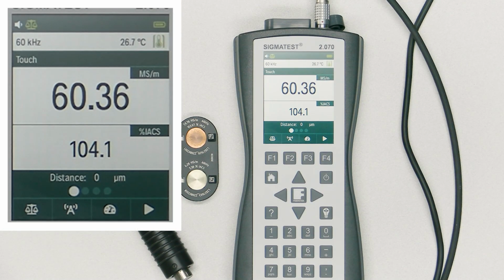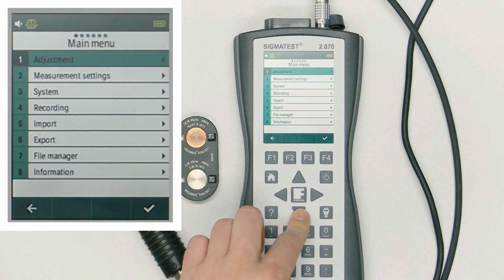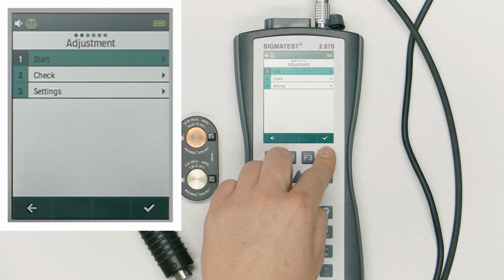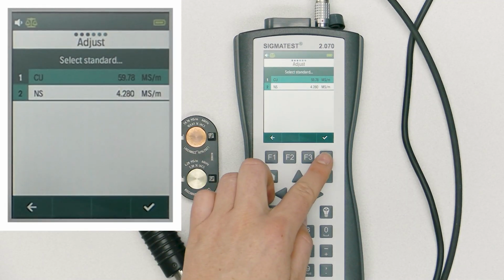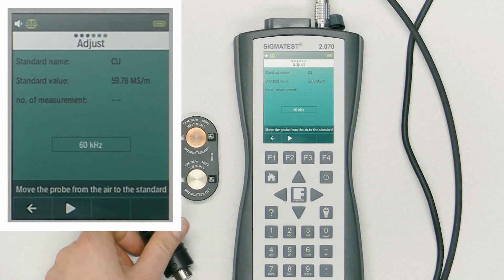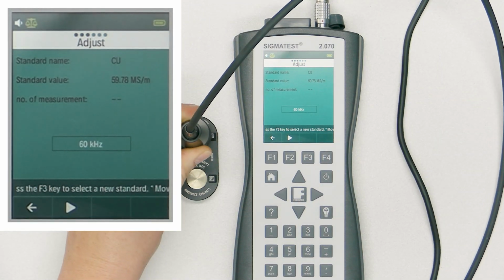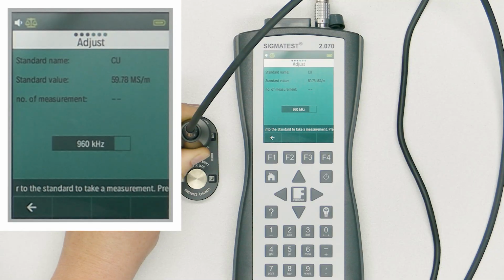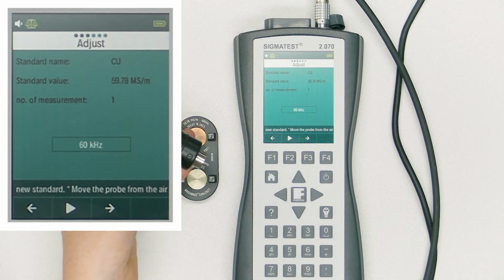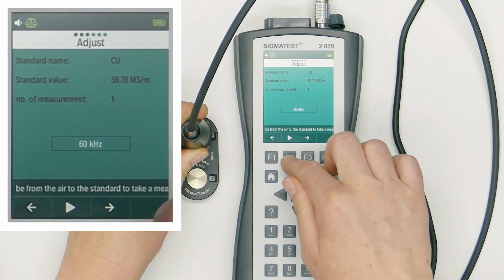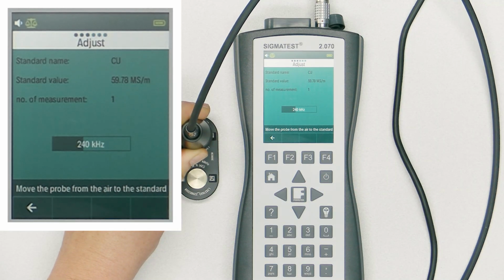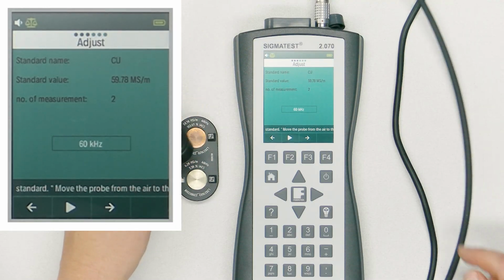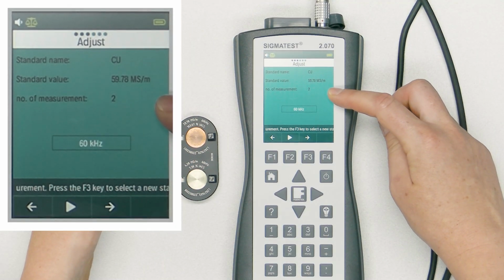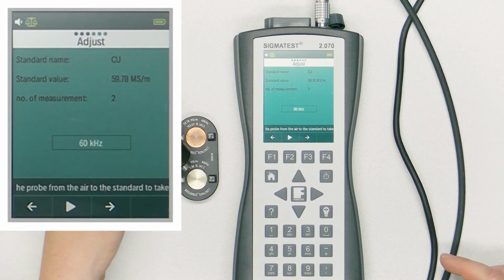I start the adjustment under the following path: Main menu, Adjustment, Start. Select the first standard. In this case, it's copper. Put the probe on the standard and select F2. Lift the probe. In case another measurement must be performed, press F2 again. Here you can see the number of measurements. It is recommended to perform 3 measurements. So we measure again.